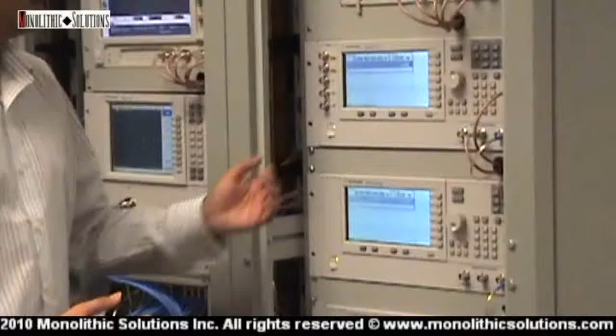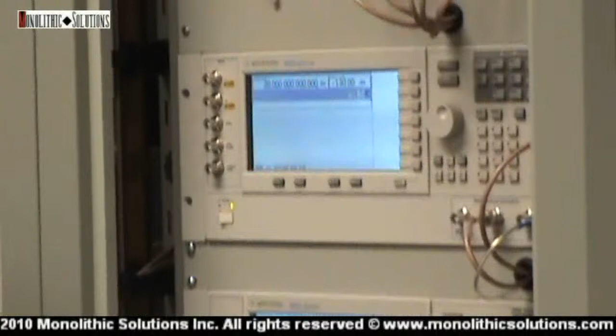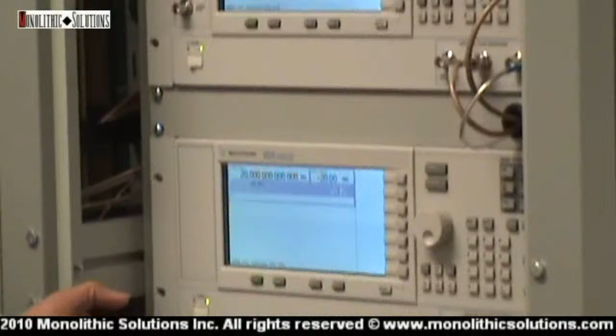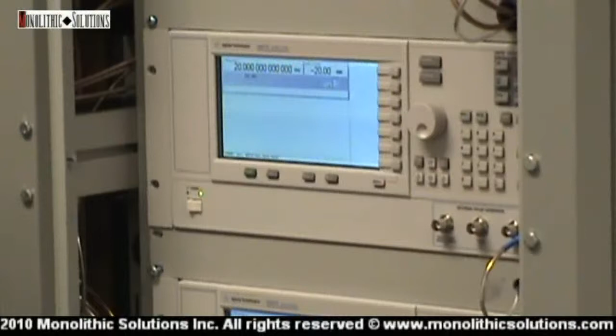This is a vector signal generator that can modulate a carrier up to 20 GHz with pulse modulation, complex waveform generated by built-in arbitrary waveform generator. These are 2 scalar signal generators that can generate clean RF sources, tones up to 20 GHz with phase noise less than -130 dBc per Hz at 1 GHz with 10 kHz offset. This sums up to 3 RF sources in the system that makes it possible to test an IQ receiver.